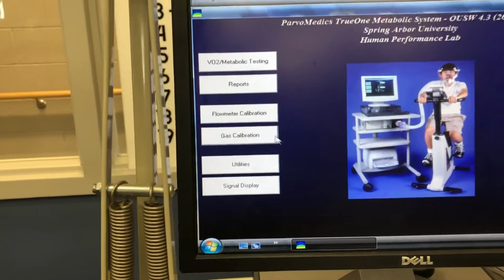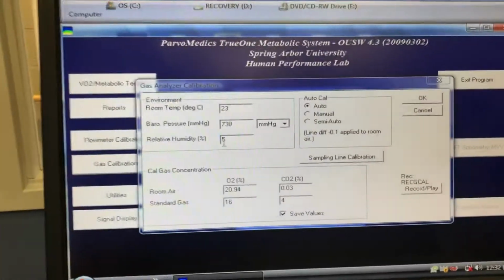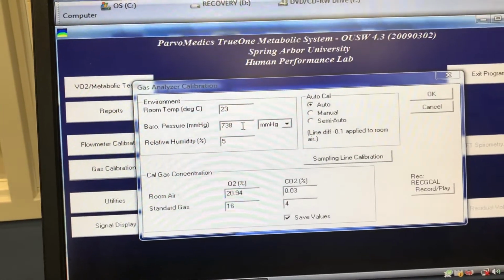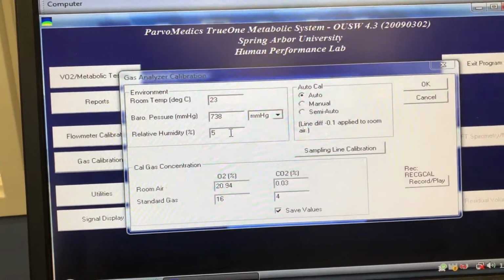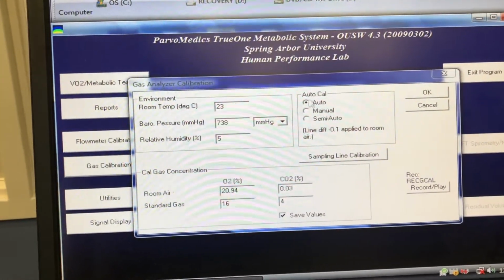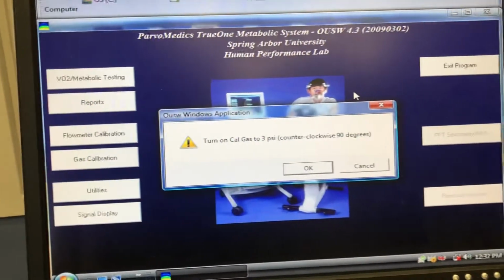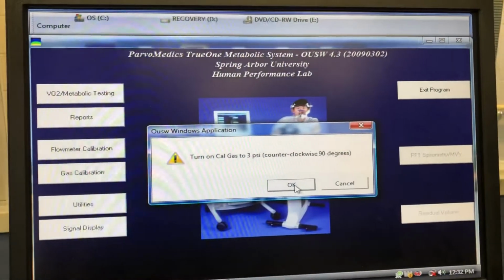We go back and hit gas calibration, checking that barometric pressure, temperature, and humidity are all the same as the black box, and they are, so we hit OK. Then we turn on the gas, repeating everything, going to the 12 o'clock position, and now we're hitting OK.